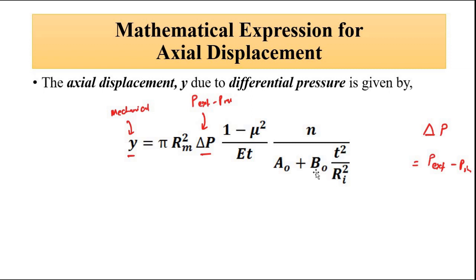A0 and B0 are constants which depend on the type of material selected, whether it is alloy, rubber, or plastic. This is specified in the chart, the specification sheet provided by the manufacturer along with that particular sensor. T is the thickness and Ri is the internal radius of the bellow.